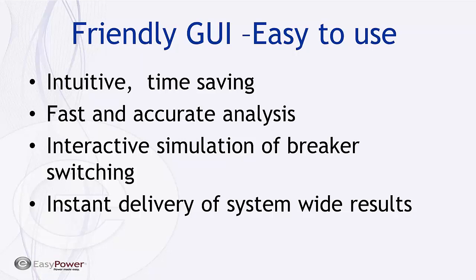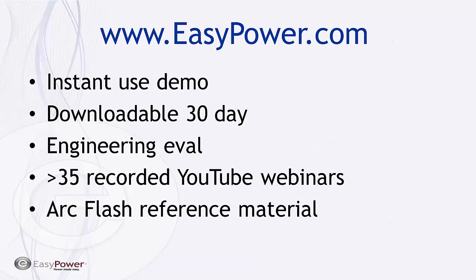Because it's part of the EasyPower suite, it uses the same user-friendly graphical user interface, which means there's an intuitive flow that in itself makes it easier and a time saver, because you don't have to be a power user on a day-to-day basis to be able to get protective and dependable results every time you use the tool. And it does permit the interactive simulation of breaker switching, and because it works in conjunction with the Power Protector module, there is an interactive ability to see what the impact is on arc flash as we're doing the adjustment and coordination procedures.